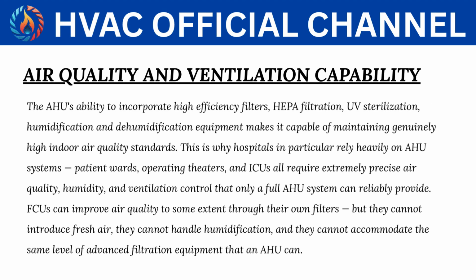The AHU's ability to incorporate high-efficiency filters, HEPA filtration, UV sterilization, humidification and dehumidification equipment makes it capable of maintaining genuinely high indoor air quality standards. This is why hospitals in particular rely heavily on AHU systems. Patient wards, operating theaters, and ICUs all require extremely precise air quality, humidity, and ventilation control that only a full AHU system can reliably provide.